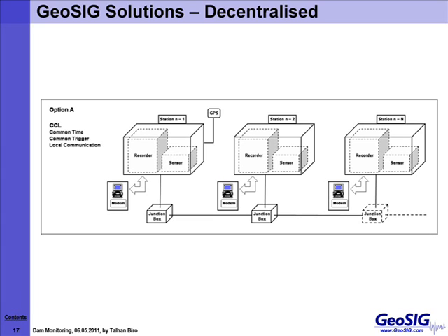So basically with this kind of connection, or what we call it as interconnection, we will have a common time that is distributed to each recorder, each measuring point, and then a trigger information in case any recorder, any digitizer is triggering due to a level exceedance. Then all the others will know about this and start to record at the same time. And then communication is achieved by visiting or instrumenting each and every recorder separately to be able to interact with the unit.